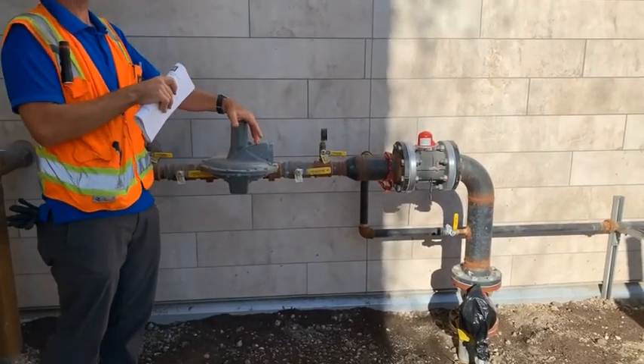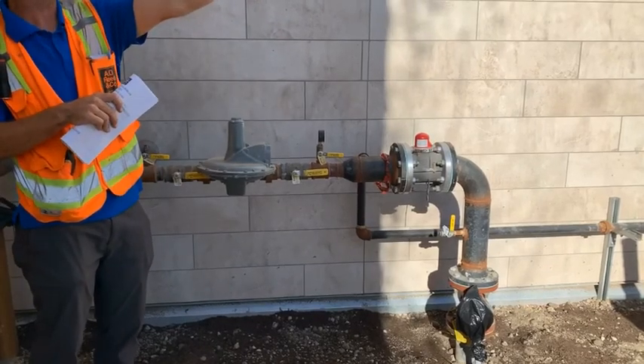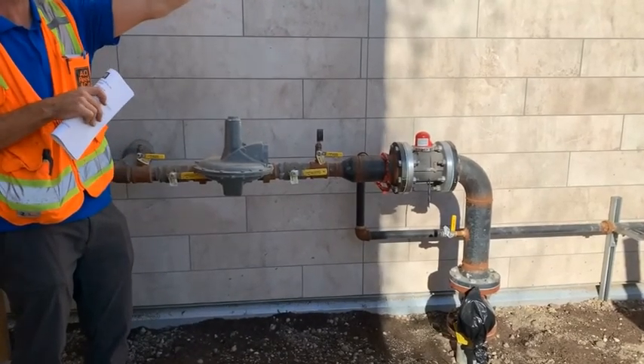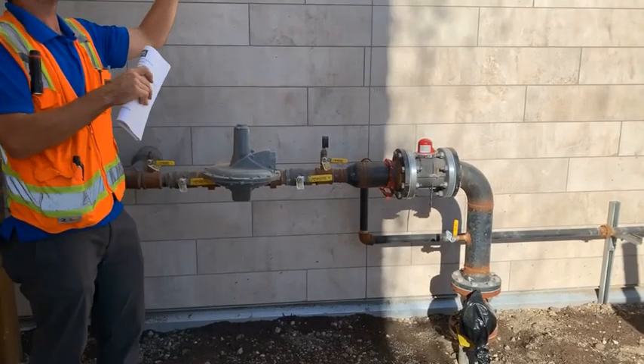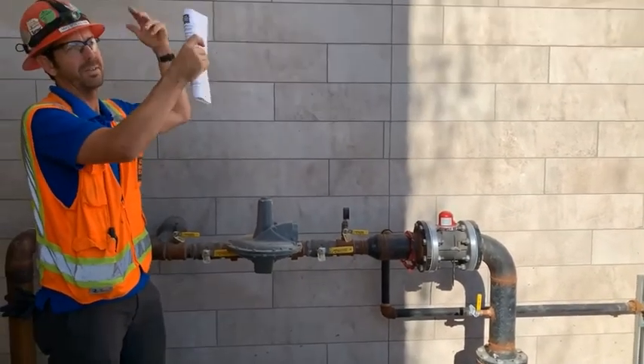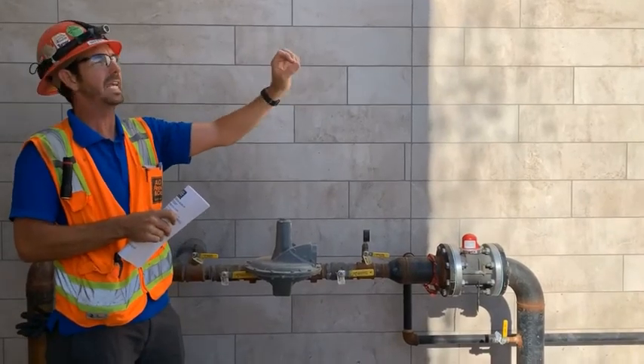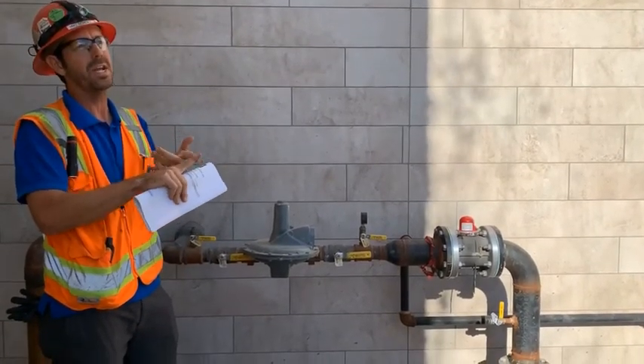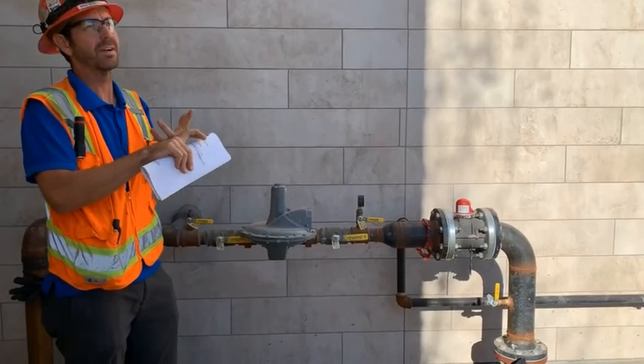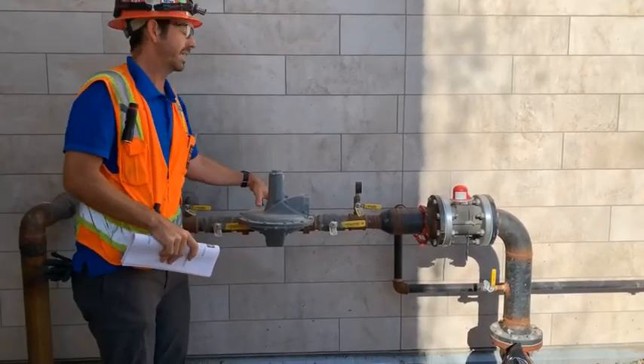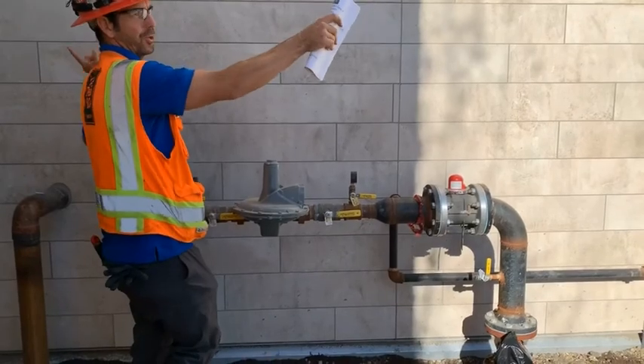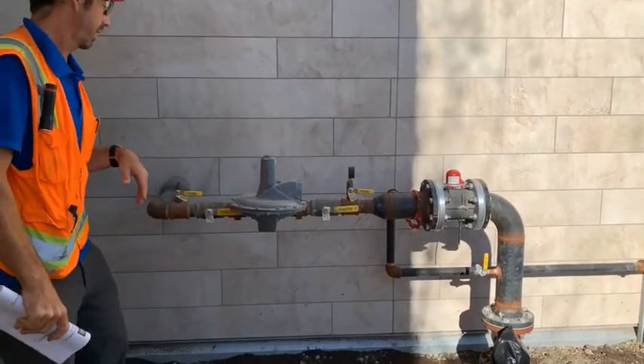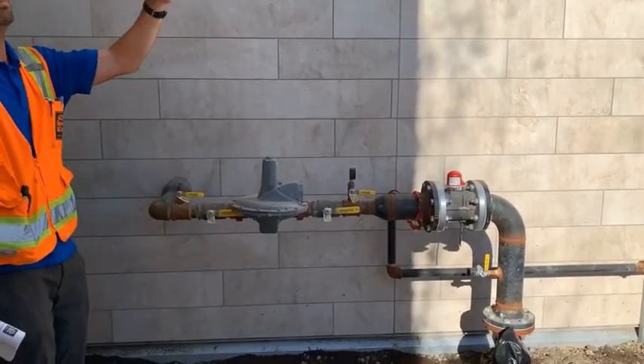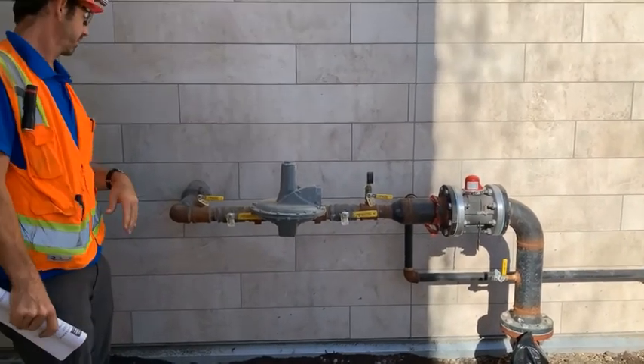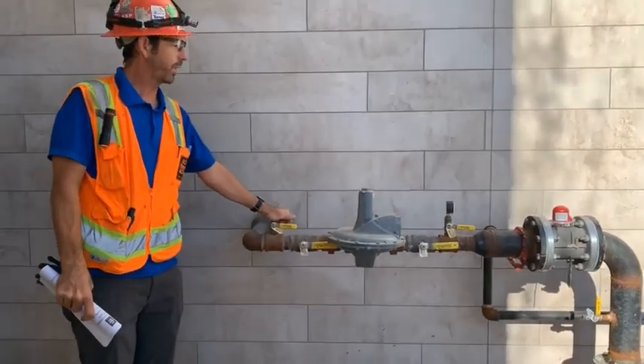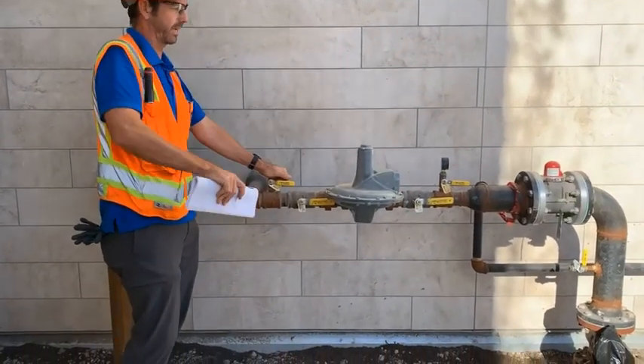In building A, that we see right over here, this fenced area, that's one of the 2 RA units, the people that are in charge of watching all the students in the rooms. That's one of the rooms. So each one of those rooms has a gas range and a gas dryer, okay? So that's where this gas feeds. Each room, 2 drops in each room, okay? There are local shutoff valves in each room. We can go over there and put eyes on those. And then another test port here for downstream if you ever have to set the reg.